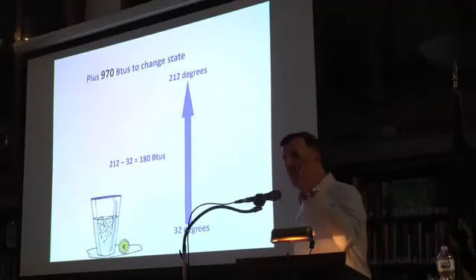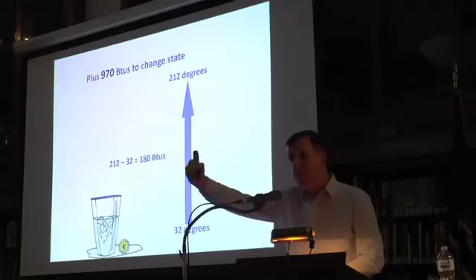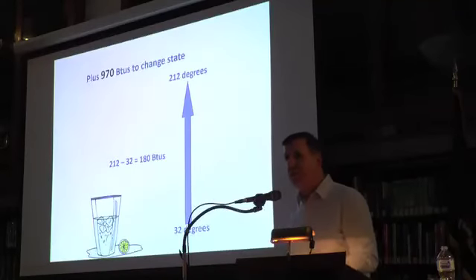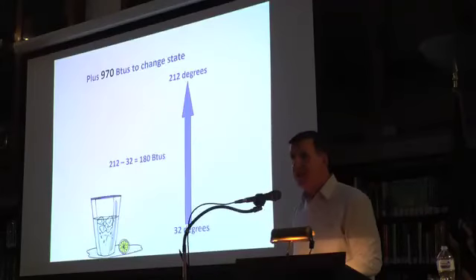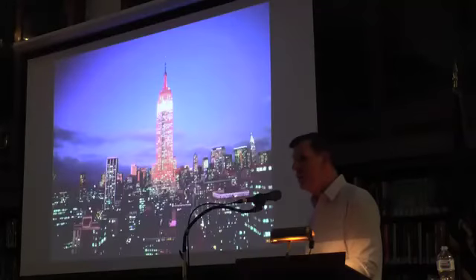And that's there at 0 PSI. The only reason you need pressure is to overcome the pressure drop as the steam travels through the piping, which is based on insulated pipe and not more than 2 PSI, which they decided on December 19th, 1899 would be the standard. It's called the 2 PSI standard. This is why sensible heat and latent heat are 2 different things. This is why it's the latent heat that heats the building, and it's there for you at no pressure. This is how they heat the Empire State Building at 1.5 pounds of pressure.